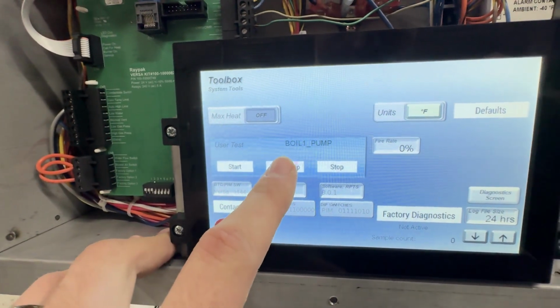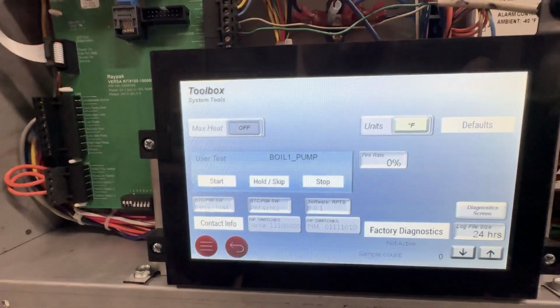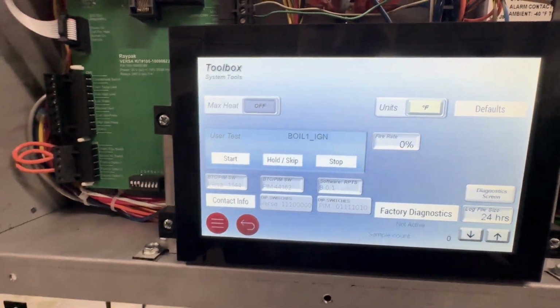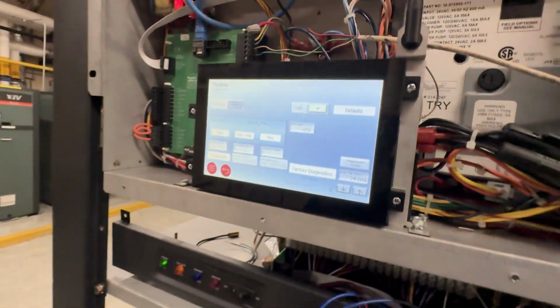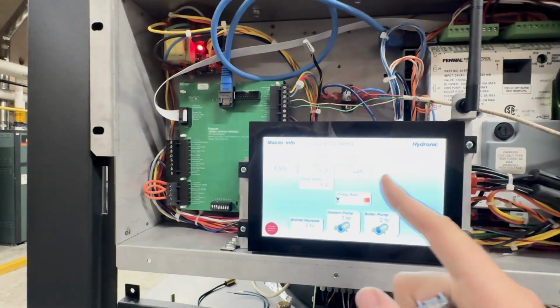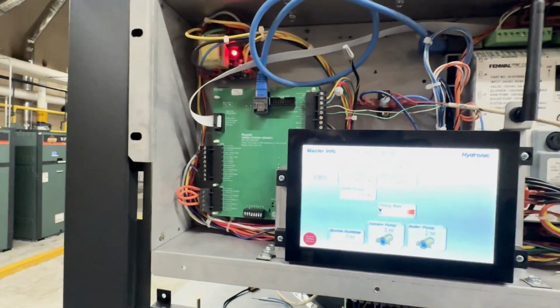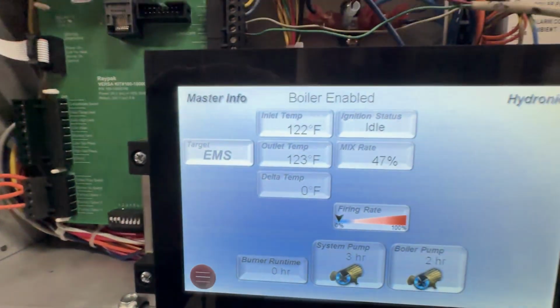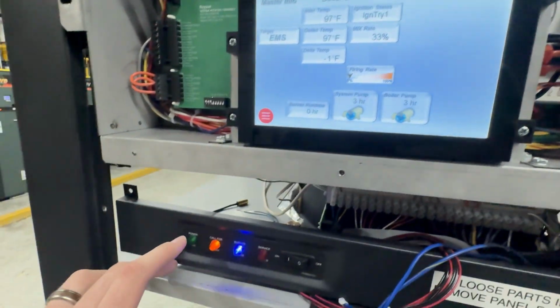There's the pump. Go straight into ignition. While we wait for the pre-purge and the gas valve to ignite, we're gonna keep an eye on our inlet and outlet. Our gas valve just opened. Ignition try 1. Looks like the flame is proved.